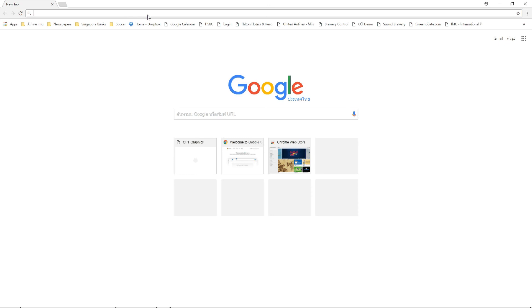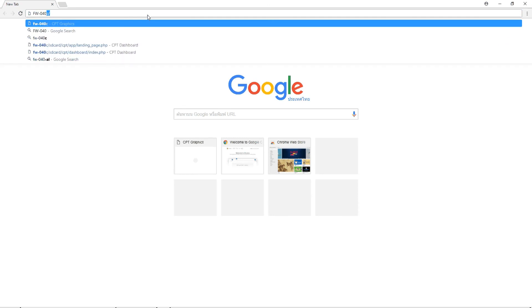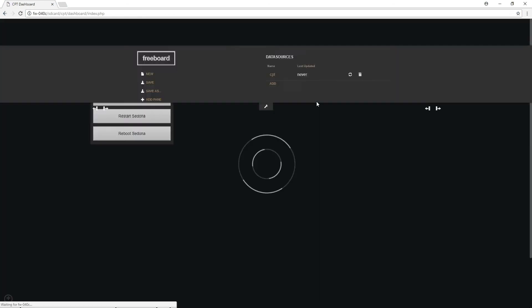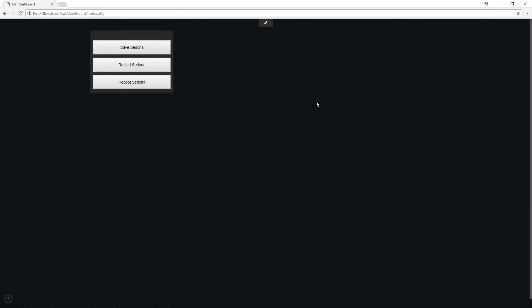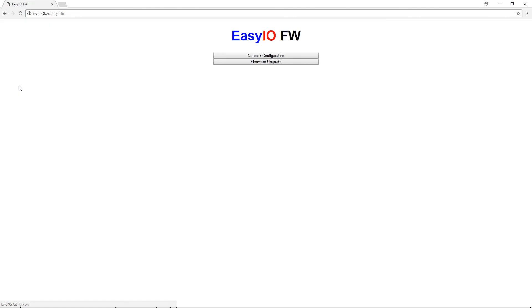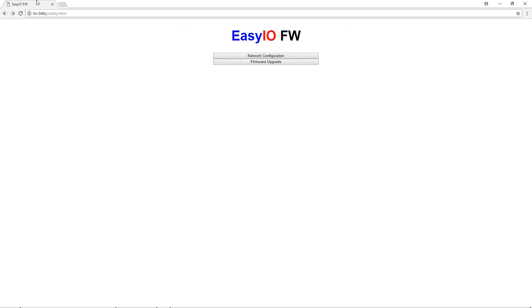So let's go into FW 040C forward slash. It asks me to log in. And all the FW controllers have a built-in dashboard. So our VAV controller has this preset and you can actually have a full utility driven through here to cover just about any type of VAV application. So you can edit anything that's in here.